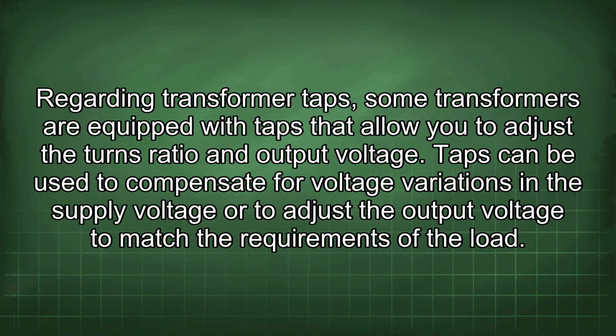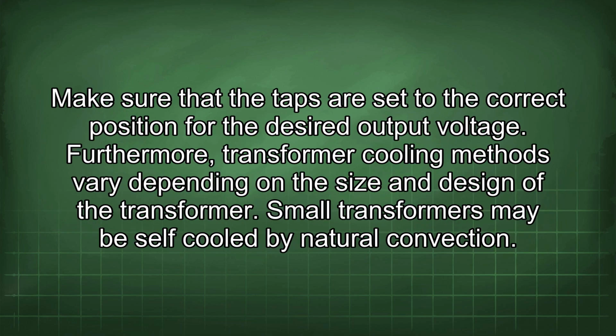Regarding transformer taps, some transformers are equipped with taps that allow you to adjust the turns ratio and output voltage. Taps can be used to compensate for voltage variations in the supply voltage or to adjust the output voltage to match the requirements of the load. Make sure that the taps are set to the correct position for the desired output voltage.